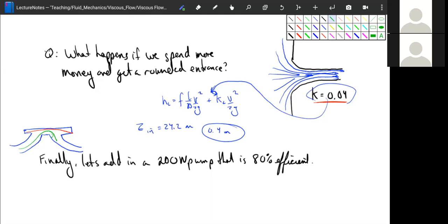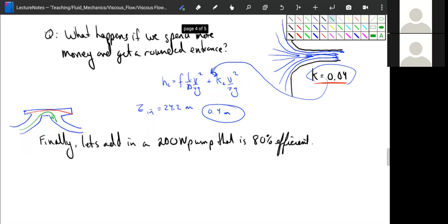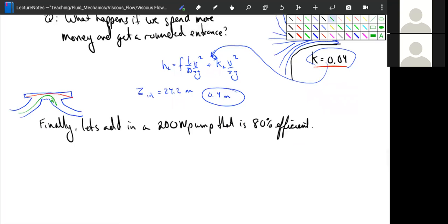Obviously, you're going to have flow separation. You're going to have all kinds of turbulence added, and you have a natural narrowing, in addition to any kind of flow separation that's occurring. And so the losses on diaphragm valves are much higher than, say, for a ball valve, which can be quite low when it's completely open. Butterfly valves are somewhere in between, but are cheaper than a ball valve. So yeah, there's lots to consider when you're building a fluid system.